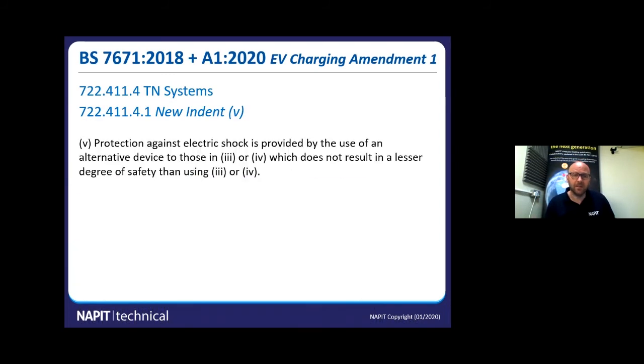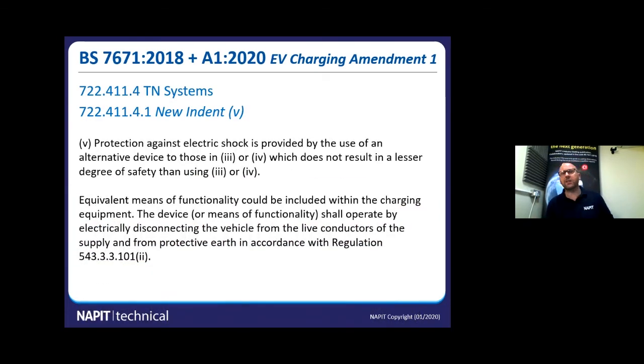The next indent, and the last one, was introduced really to allow EV manufacturers some flexibility to design different solutions. So the first one is very exact: you must measure between line and neutral, and it must do this, this, this, and this. This one allows manufacturers to build safety into their equipment as long as it's no less safe than the previous conditions that we've just talked about. So again, the amendment is providing flexibility for this future growth that's happening with EV charging, and we're going to see these new solutions come out.